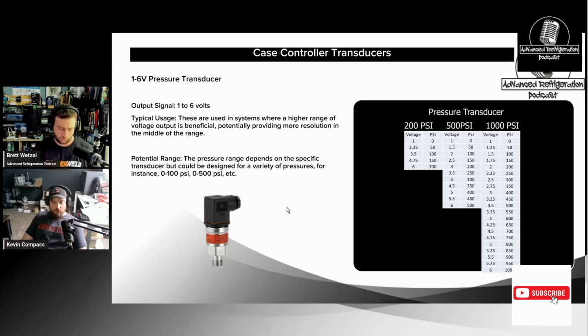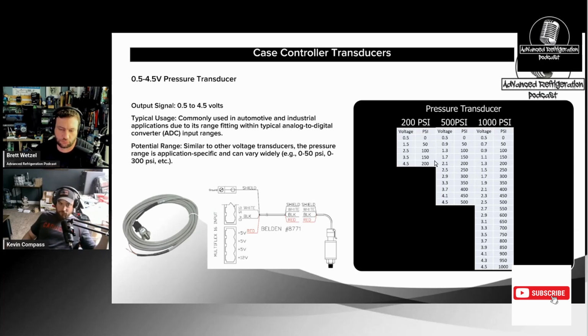Okay. Now you want to take your meter and go from ground to the signal wire, which is generally a white wire. Not all the time, because there's been a bunch of this, got me last year. Some transducers, they switched some cables on and caused some issues. So you want to find that signal wire, and go from ground to signal. You should have a DC signal on there. It's going to be linear from whatever it is. If it's 0 to 100 psi and it's a 0.5 to 4.5 transducer, at 0.5 volts DC, it would read 0 psi on the controller.